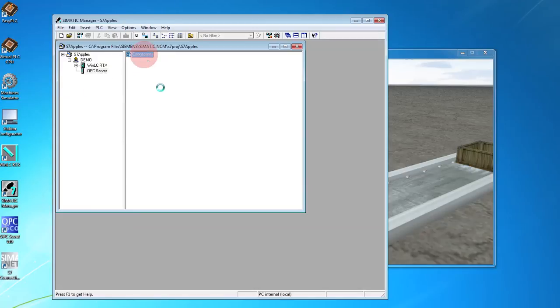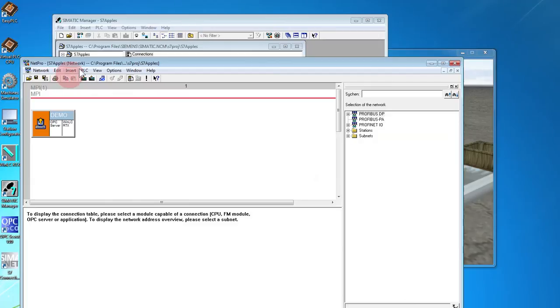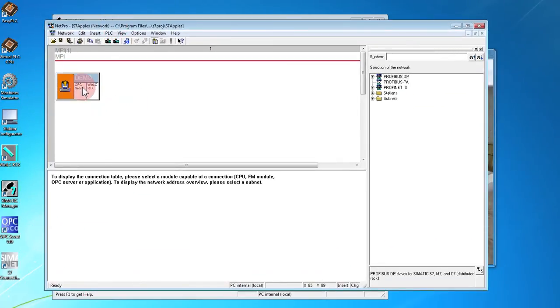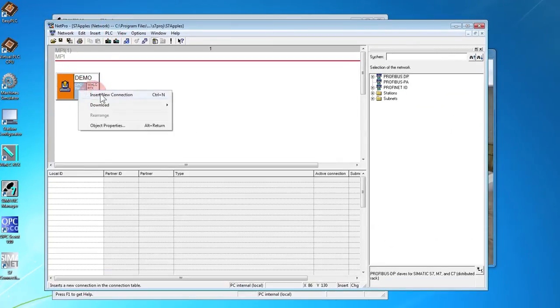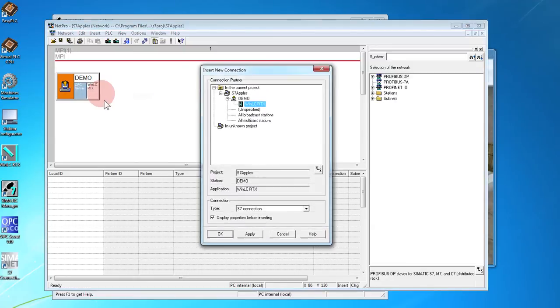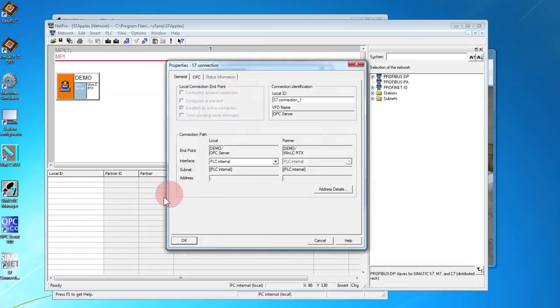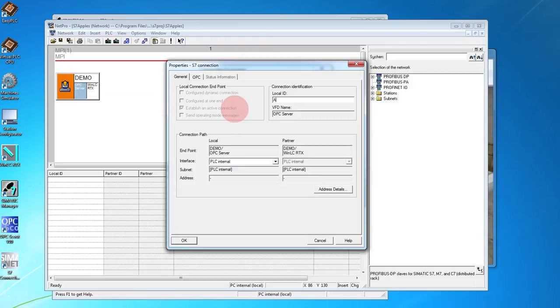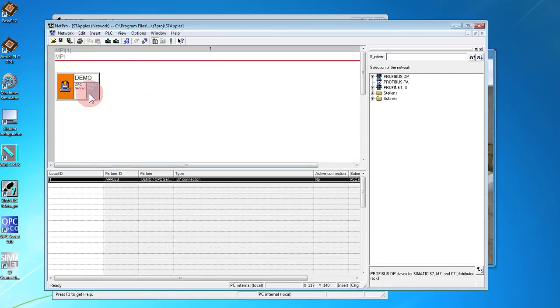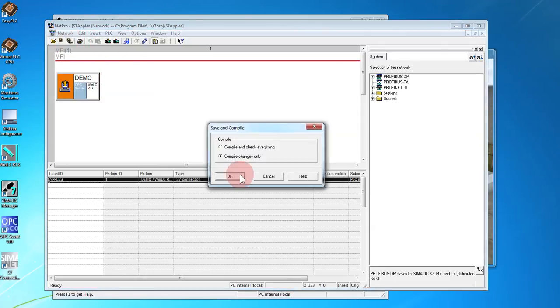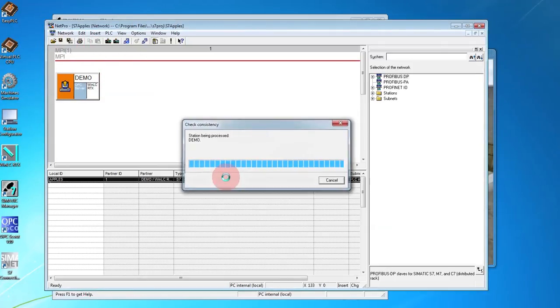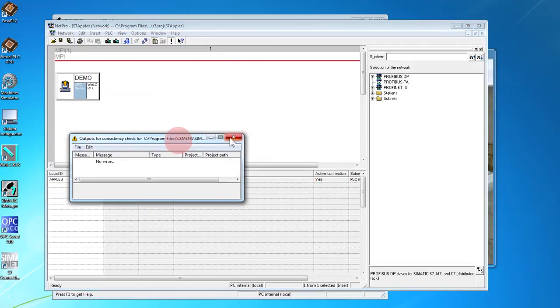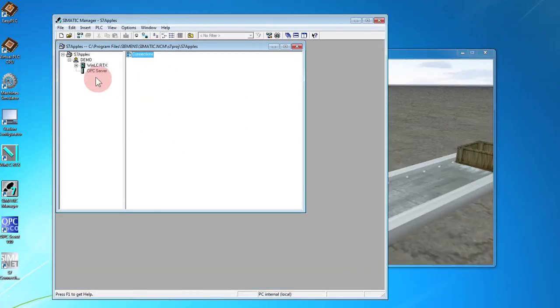Set up an OPC connection, which brings up NetPro. Right click on the OPC. Set up a new connection. It's going to be S7 connection. Everything's default there, just pick OK. In here we want a local ID. That's going to be our OPC topic name. Save and Compile. Close this.